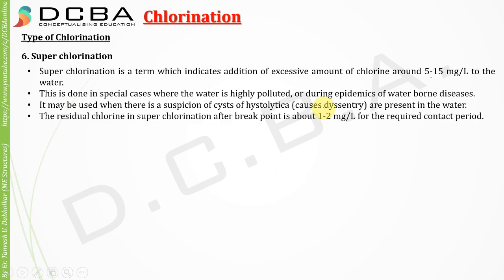The residual chlorine in superchlorination after breakpoint is about 1 to 2 milligrams per liter, and it is kept for some required contact period. But this residual chlorine is very high and it is going to impart a very bad taste and odor to your water, which may leave the water such that you cannot drink that water.